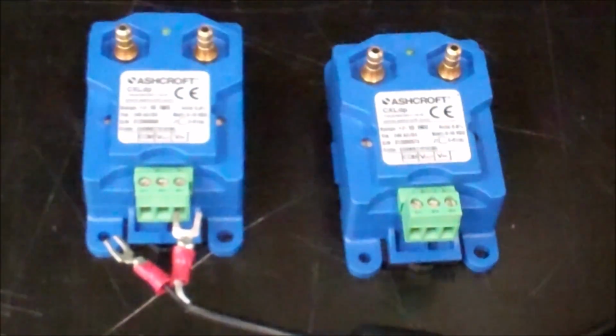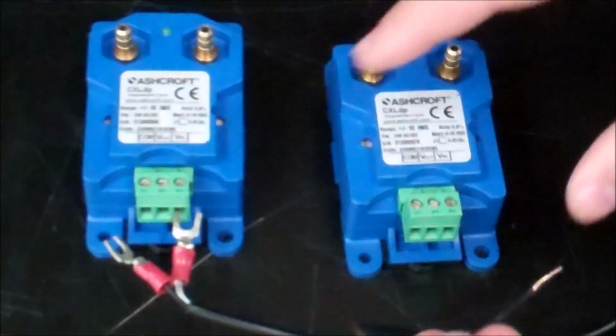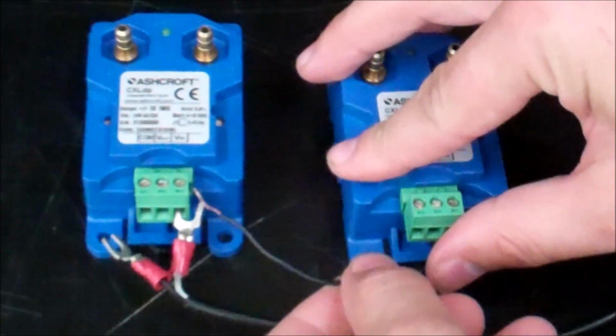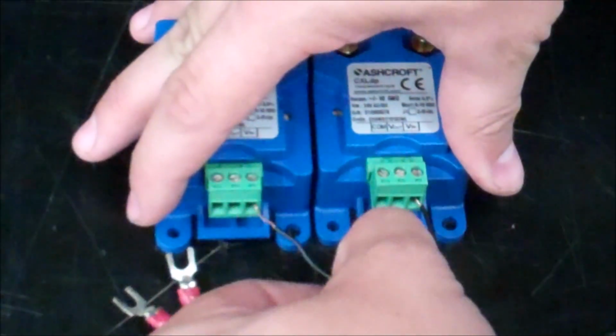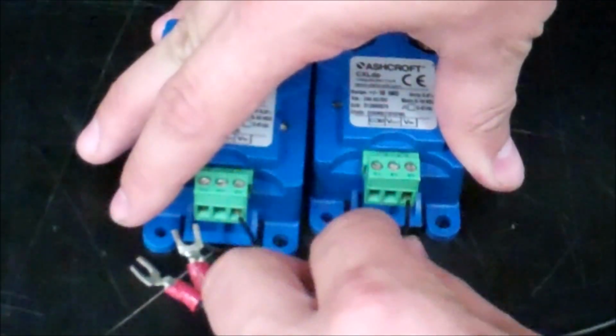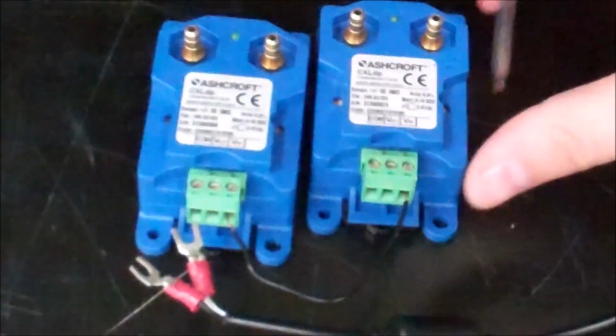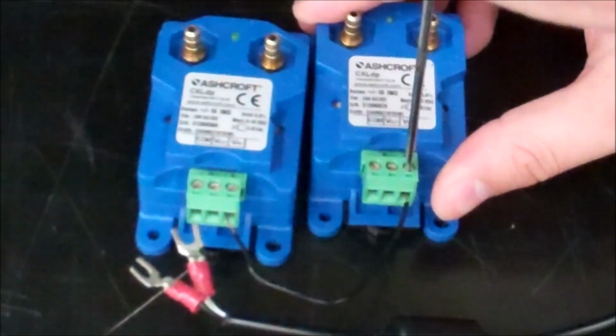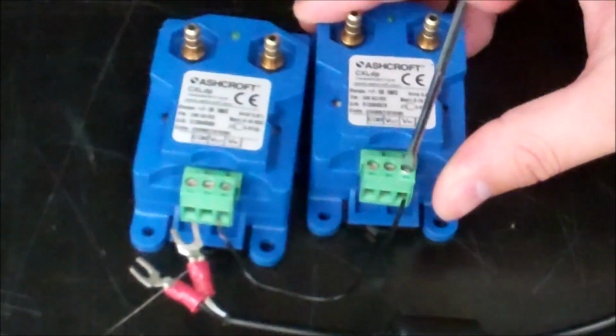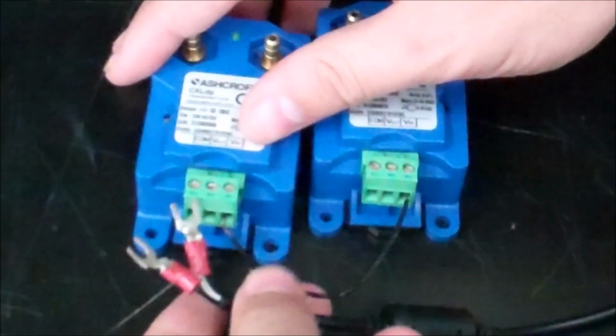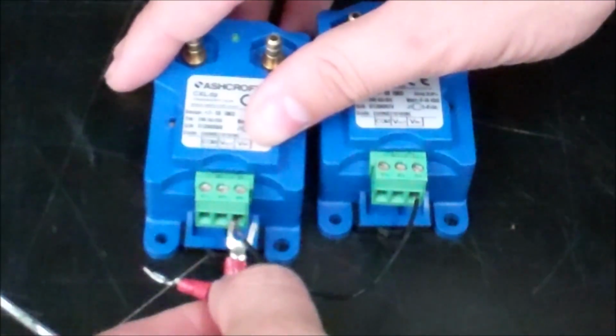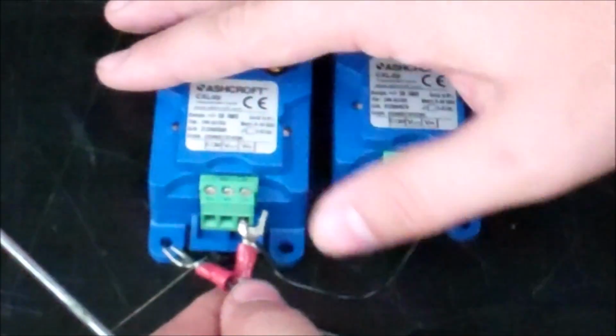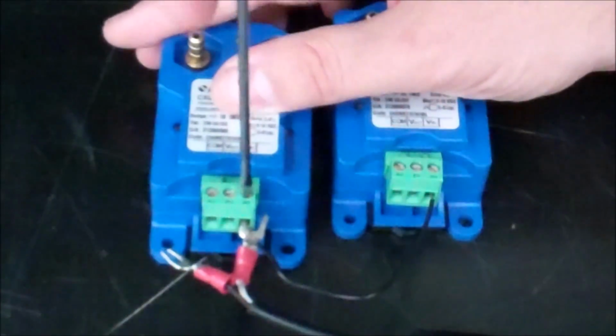Now I'm going to take my jumper wires and I'm going to jump the V in of the one pressure transducer to the V in of the other pressure transducer. I'm going to go ahead and tighten the side on the V in first on this right pressure transducer. And then I'm going to connect the V in of this pressure transducer together with the power supply and tighten it.